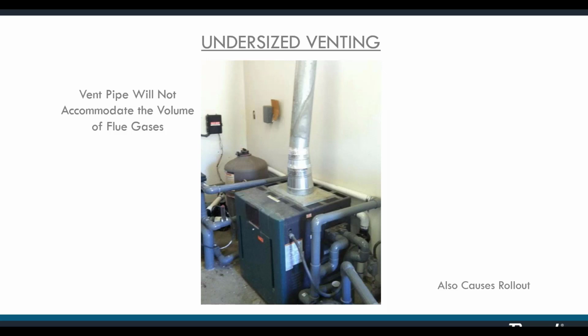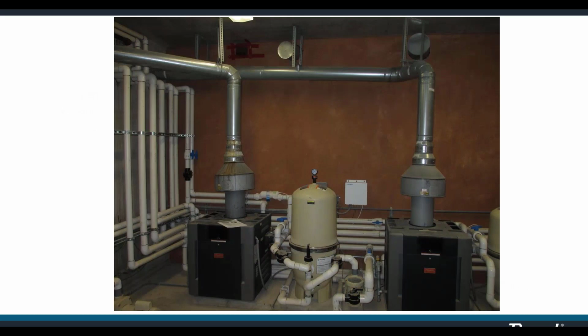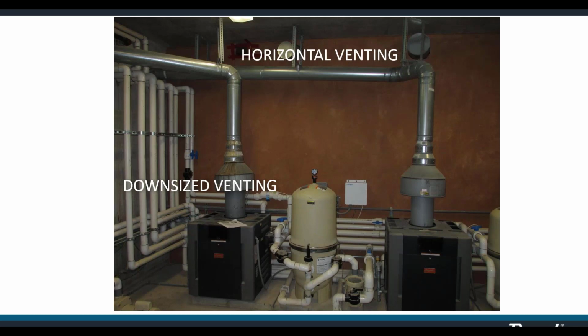Undersized venting is also a problem. If the vent is just too small to accommodate the gases being produced, they won't get out of their own way. This leads to internal condensation as well as other issues like rollout and sooting. Now here's some problem venting. First of all, it's downsized, which is a problem, but look at the horizontal portions. You know, convection pulls the hot gases upward, not sideways. Hot air rises, so there's nothing to pull the fumes horizontally. You can use horizontal venting, provided that the rise is 1/4 inch per foot. So for every 4 feet of horizontal vent, the downstream end must be at least 1 inch higher than the other end. This way, the flue gases always have an upward path to travel.